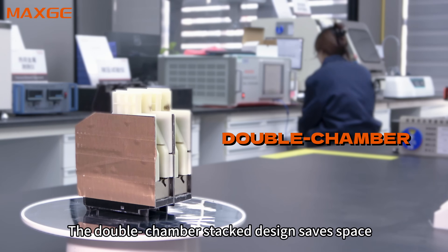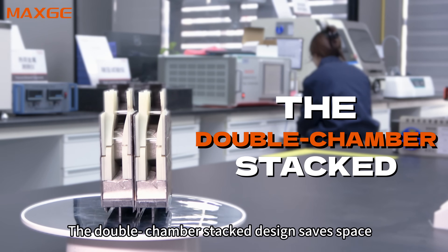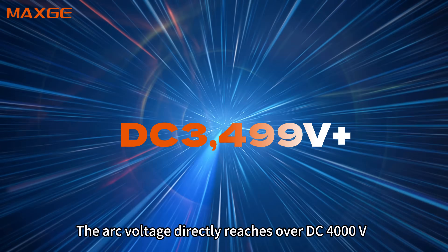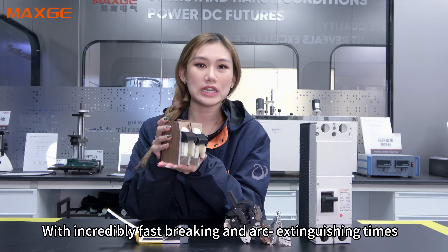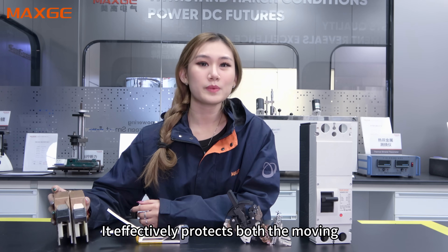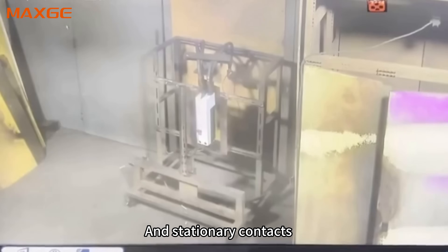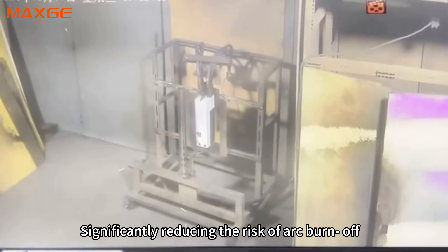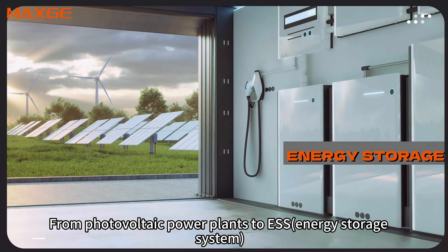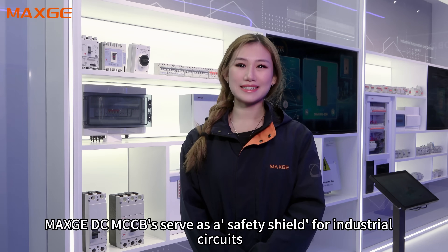Third, the arc-extinguishing system: the double-chamber stack design saves space, while independent exhaust prevents interference. The arc voltage directly reaches over DC 4000V with incredibly fast breaking and arc-extinguishing times, effectively protecting both the moving and stationary contacts and significantly reducing the risk of arcing. From photovoltaic power plants to energy storage systems, MAXGE DC MCCB's serve as a safety shield for industrial circuits.